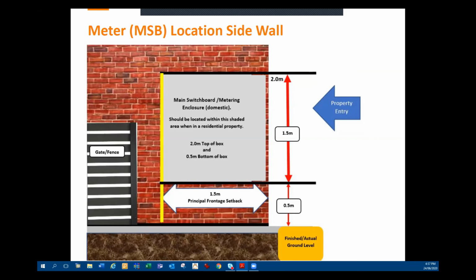This indication is just generally that the meter box should be located within the shaded area when it's within a residential property. And you've also got to take into account the finished or actual ground level. In some cases that ground level may need to be built up for the time of connection, and then extra paving or landscaping happens after that time. We'll just need to make sure that it ends up at the correct level.